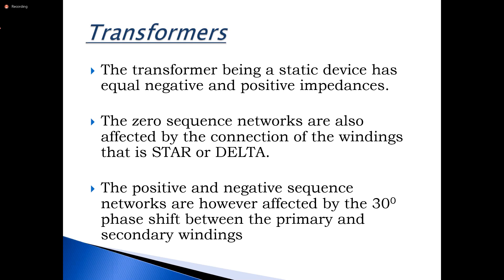So we must also know that the zero sequence currents cannot flow unless there's a path to ground, as we just explained. So the only winding that will allow zero sequence to flow would be your grounded star. Otherwise, it won't flow. If it's a delta winding, you will not have zero sequence. If it's an ungrounded star, there will be no zero sequence. So the only winding that will allow zero sequence would be your grounded star.